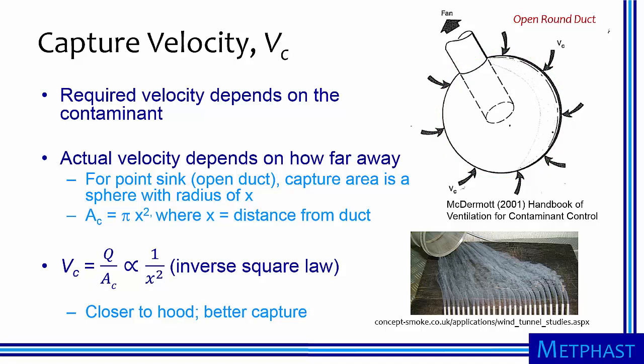The capture area can then be expressed as pi times x squared. Capture velocity is equal to the air flow divided by the capture area, which is dependent on distance squared. Thus, the capture velocity is related to 1 over distance squared, or the inverse square law. The bottom line is that capture velocities are high near the duct and rapidly diminish with distance away from the opening.